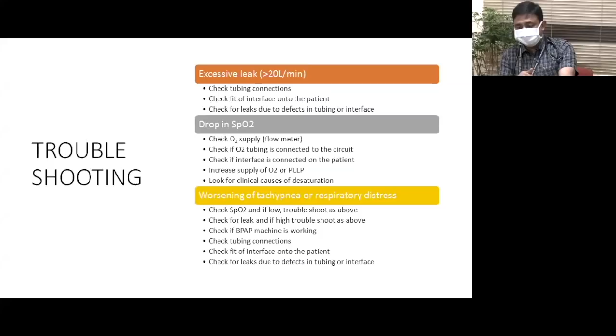Worsening of tachypnea or respiratory distress: again, we need to check the oxygen and the flow and troubleshoot as in the above 2 sections. We need to check for leak and troubleshoot that. We need to check if the BiPAP machine is working, check the tubings, check the interface, and check for leaks in the entire circuit. Tachypnea, as I alluded to previously, is multifactorial.